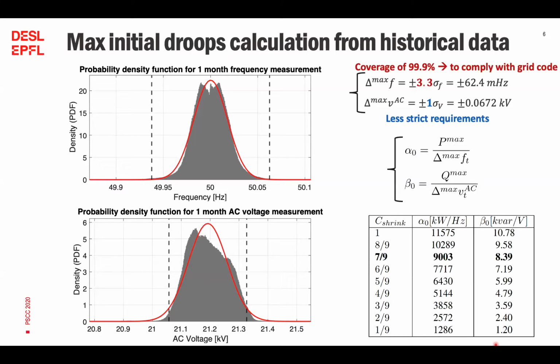And as you can see in the table, we have defined these values for different C shrink factors. This factor reflects the total available power that the grid can expect from the system. In fact, for battery system applications, a peculiarity is the modularity of the system, meaning that the system can be operated with a reduced number of strings configuration. For example, in our particular case, we have a total number of 9 strings, but as you can see from the bold values, we have used a configuration with 7 strings. In fact, all the experimental results I will show you later on will be based on this setup.